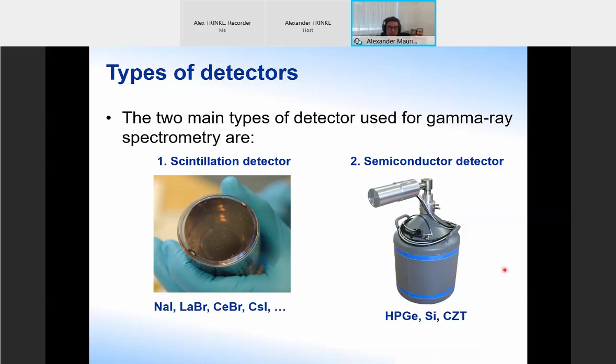What you see here would be a typical example of a side-facing high purity germanium detector. Some quick pros and cons, advantages and disadvantages, of the different types of detectors. The scintillation detectors, such as sodium iodide and lanthanum bromide, are relatively low cost. You can make them in large sizes. Of course, if you have a large detector, there's a high probability that the photons will interact in there. They have fast signal processing. They are generally more robust. On the downside, they have quite bad peak resolution. Lanthanum bromide has some internal contamination, which can be inconvenient. There's also occasionally temperature instability associated with these systems, though I know newer systems have some compensation for that. So those are some pros and cons of the scintillation type detectors.